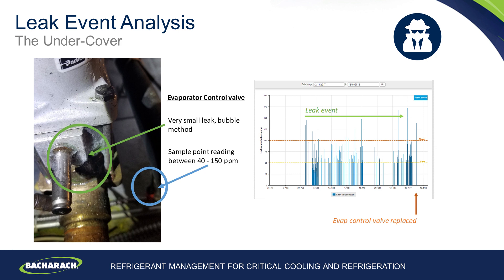During this period there was no loss of system performance, no temperature alarms from the fixture, and no low-level leak events from the system. After much perseverance and dedication, the engineer found a very small leak on the solenoid valve. Once he replaced the solenoid control valve, the leak disappeared. This was a great exercise using the resources of the BACHARACH team and the on-site refrigeration engineer to find a very small leak.